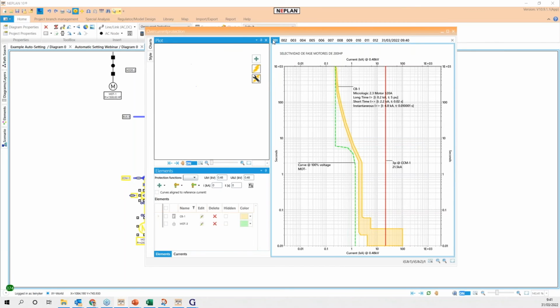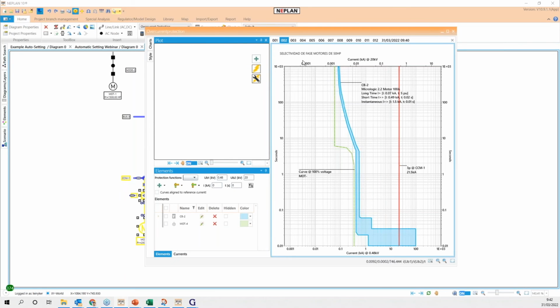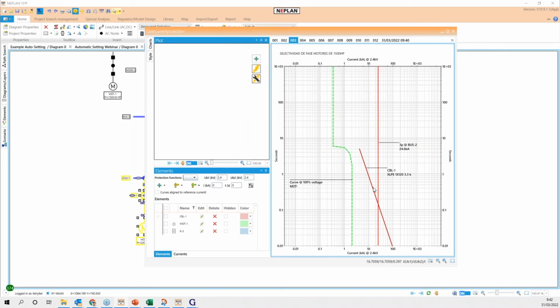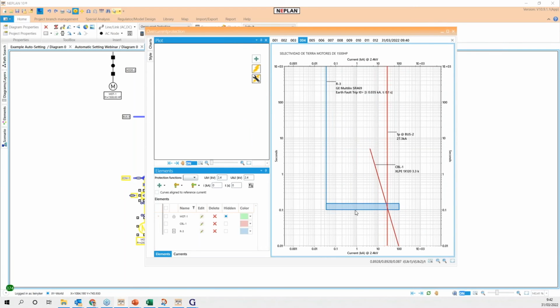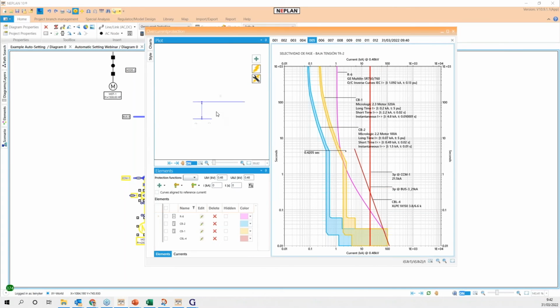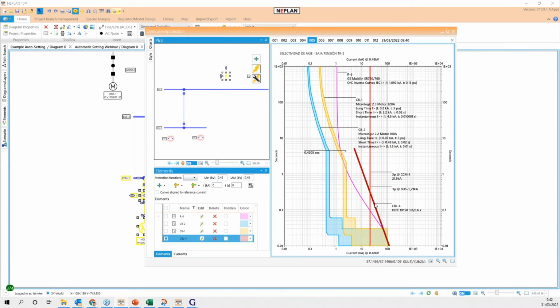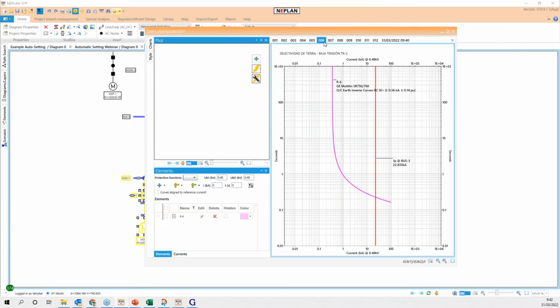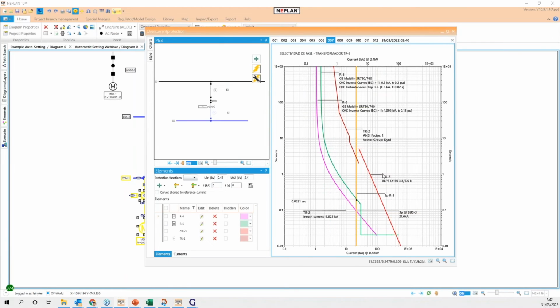So this example has many coordination principles. We have here the coordination of the machine. We have here the coordination of the motor, in this case, they have just 50 horsepower. So the coordination using the thermal limits of the cables. So the coordinations for protections in the grounding systems, coordination between the breakers and the relay, and NEPLAN allows to see in the diagram which element corresponds to that. And for sure, we also consider here the thermal limit of the cables, and many examples using the proper coordinations of NEPLAN graphically.